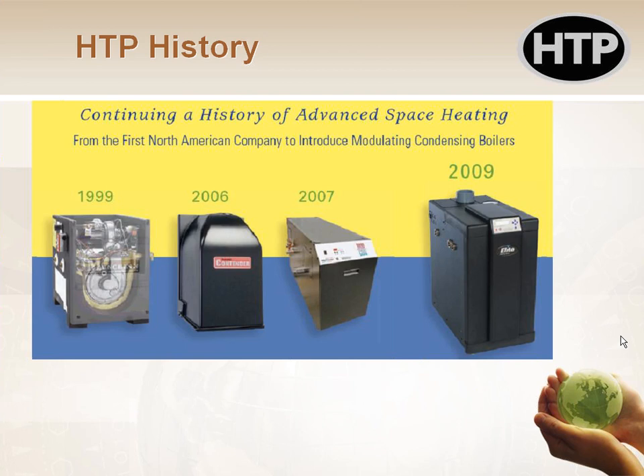Many of you probably know it as Munchkin. They were one of the very first condensing boilers to make their way to the United States 10 or 12 years ago. So they've been around for quite a while. And being first is pretty good because you get to do everything first and get your name out there. But it can also be bad because sometimes your equipment is special and it has to be installed differently than traditional stuff, in this case cast iron, and people don't understand the rules.